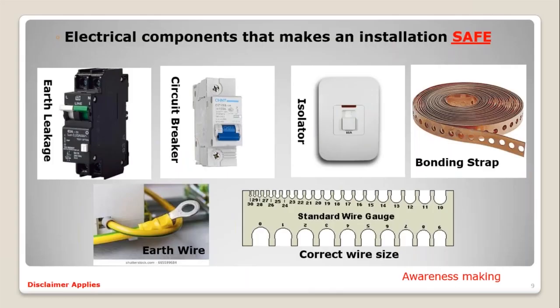To make an electrical system safe, it will need to have all these components. And if you do identify some of these components not in place, you will need to inform the homeowner of these components that are not there. Like the earth leakage that we're referring to, the circuit breaker, an isolator that's within arm's reach of the geyser installation or replacement, the bonding and the earthing that will go to the bonding, and then the correct wire size to the geyser.